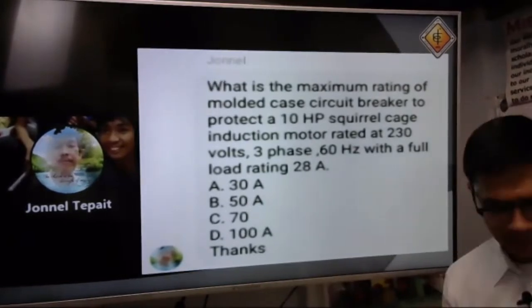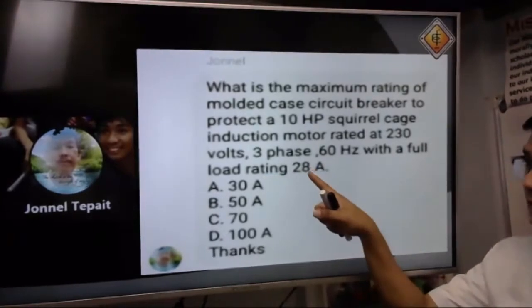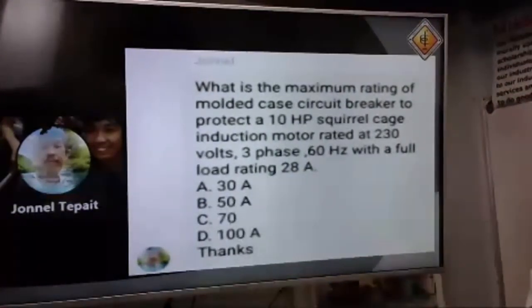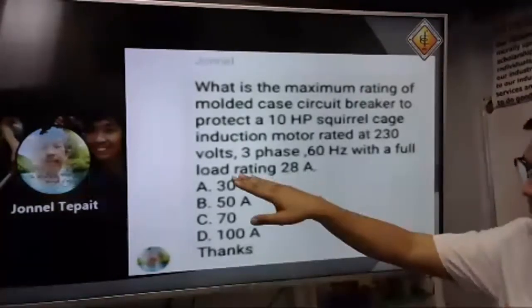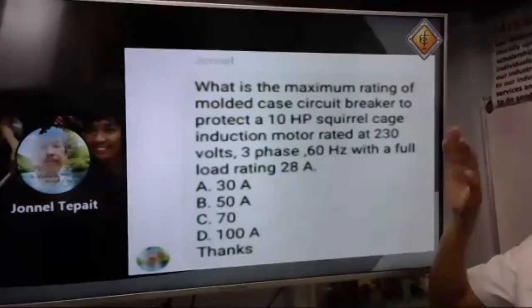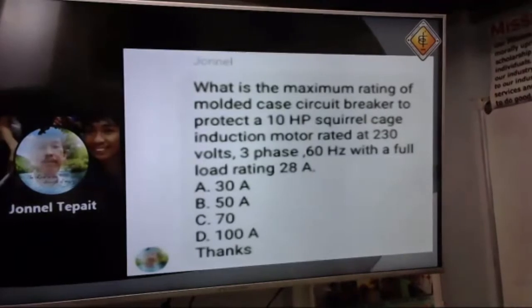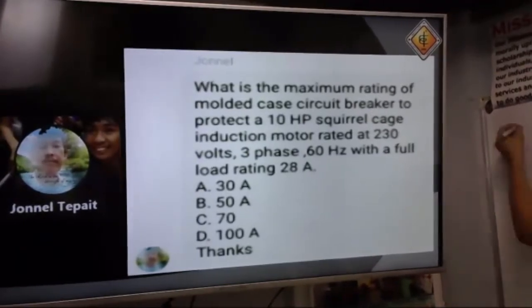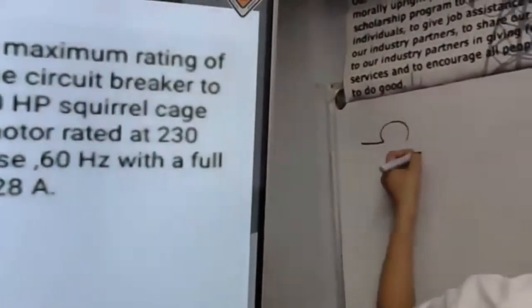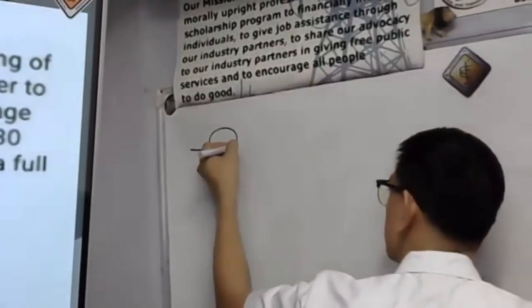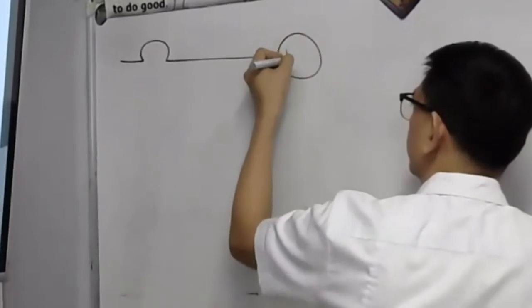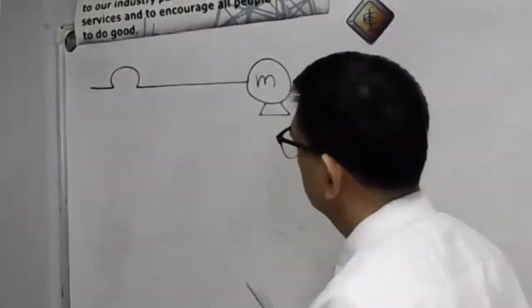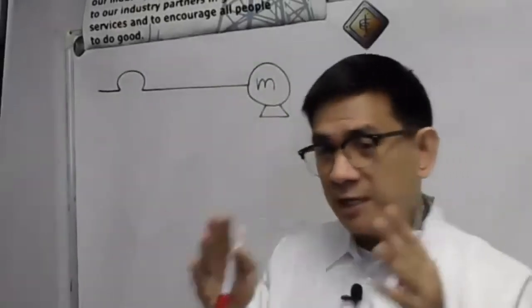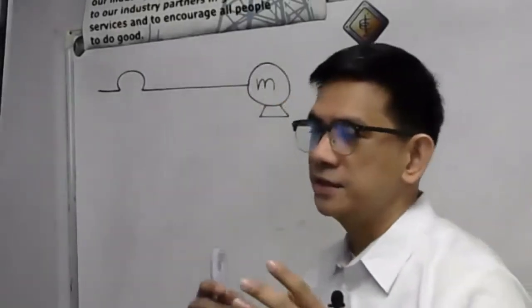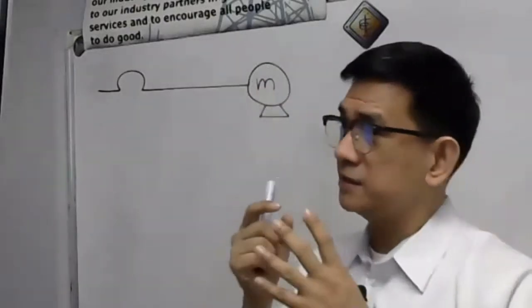Mapapadali ito kasi given na yung ating full load rating, or this is what we call the full load ampere of the motor. Actually, our only basis is this 28 amperes. What is the maximum rating of the molded case circuit breaker? Always remember, if we are sizing a circuit breaker or a fuse, we are already sizing the maximum rating. Based on the National Electrical Code in the US and also the Philippine Electrical Code in our country, it's just the same provision in terms of sizing this circuit breaker.